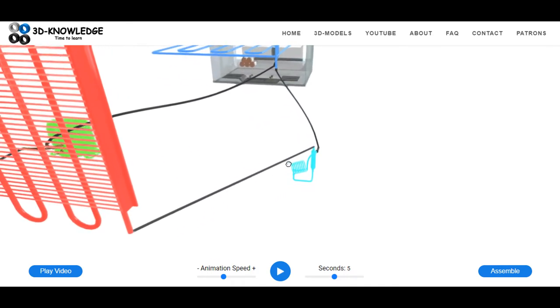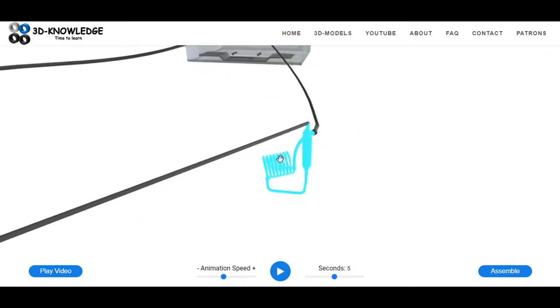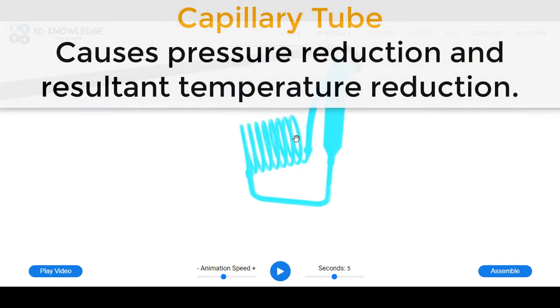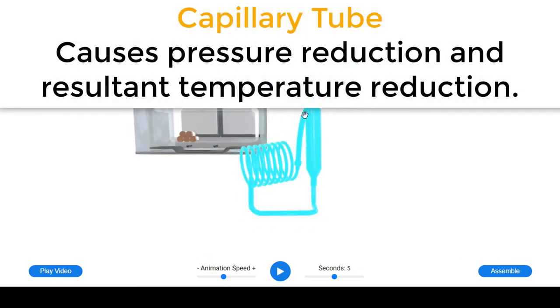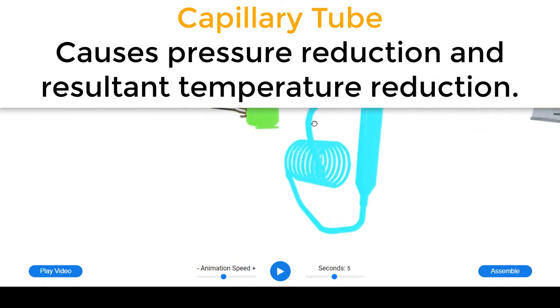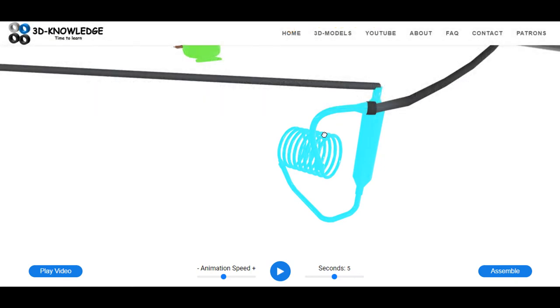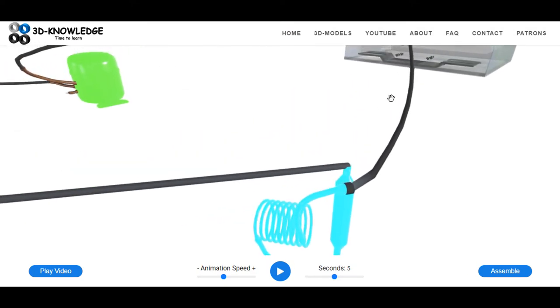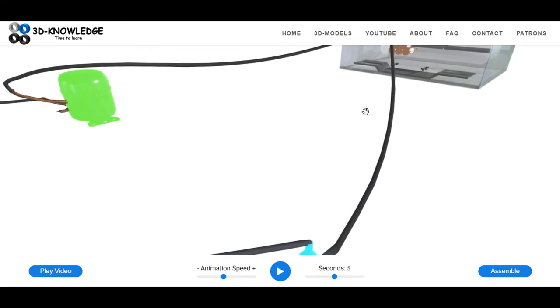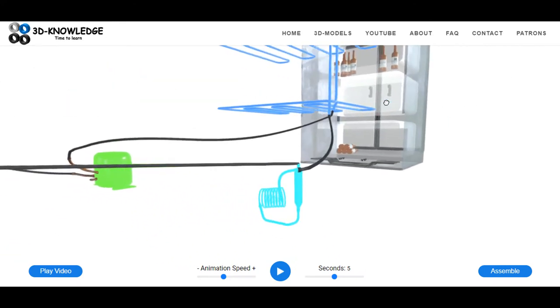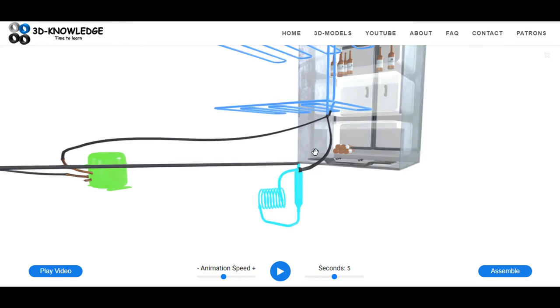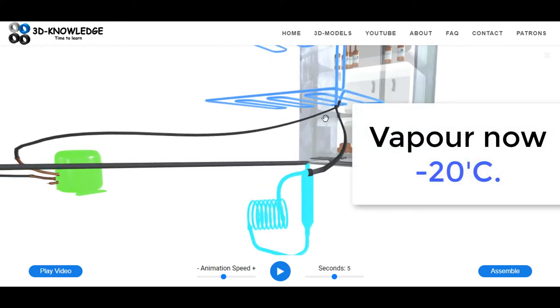Now the expansion device essentially causes a massive reduction in pressure, and because of this massive reduction in pressure, we also get a massive reduction in temperature. So remember, if you compress a gas it heats up, and if it expands it cools down. So that's exactly what we're going to do here. We're going to expand the gas so we're going to cause a massive pressure drop. This causes a massive temperature drop and it's going to be around say minus 20 degrees, minus 15 degrees. So now we have a vapor or vapor gas refrigerant at a very low temperature.